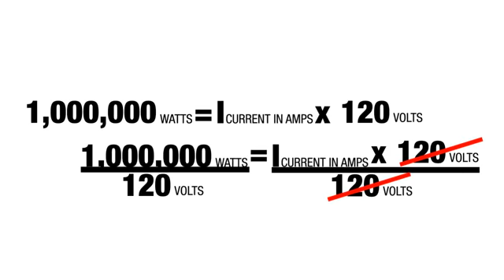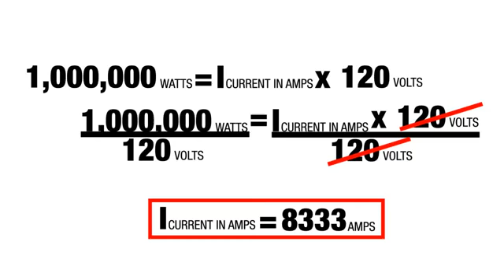If we want to supply 8,333 amps, well look, if 15 amp is about a 1/16 of an inch and 200 amp is about 1/3 of an inch, our telephone poles to supply your neighborhood or your city, to supply that 1,000,000 watts at 120 volts, you'd have cables the diameter of school buses being strung from pole to pole. That makes no sense. We can't do that. First of all, it's too heavy. Second of all, it's too expensive to do.